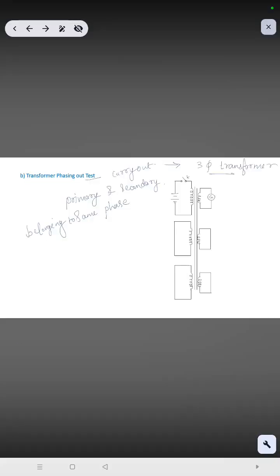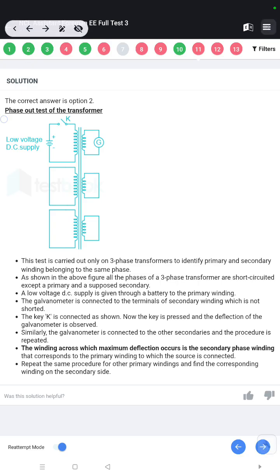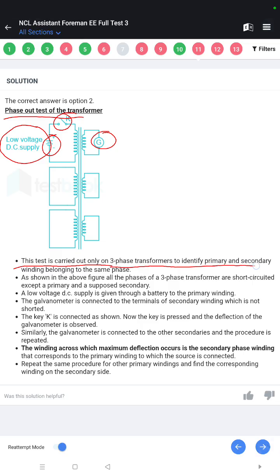Look, the phasing out test is done on a three-phase transformer, to find out whether the primary and secondary windings are both in the same phase. Phase out test of the transformer. Look, a low voltage DC supply, a switch is connected, and a galvanometer is connected on the secondary side. This test is carried out only on a three-phase transformer to identify the primary and secondary windings belonging to the same phase. As shown in the above figure, all phases of a three-phase transformer are short-circuited except a primary and the supposed secondary.